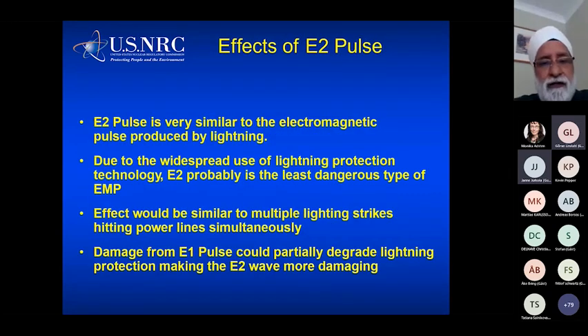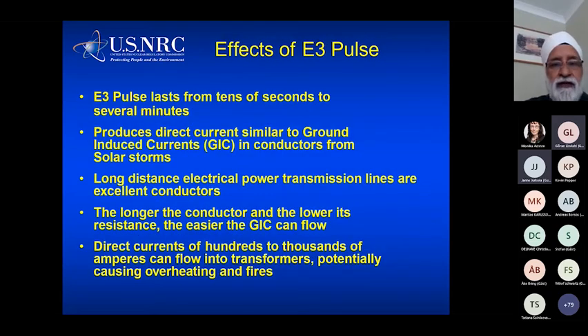Like I said, E2 is very similar to lightning, and lightning protection probably protects us from E2 type of waves. But just note that E1 could partially damage lightning protection systems, and then E2 could result in more damage. E3 pulse lasts from tens of seconds to several minutes. It produces a direct current similar to the GIC. And if you've done some research on GIC, you know what to expect. Transmission lines, transformers are vulnerable. Typically, it's an overheating issue.